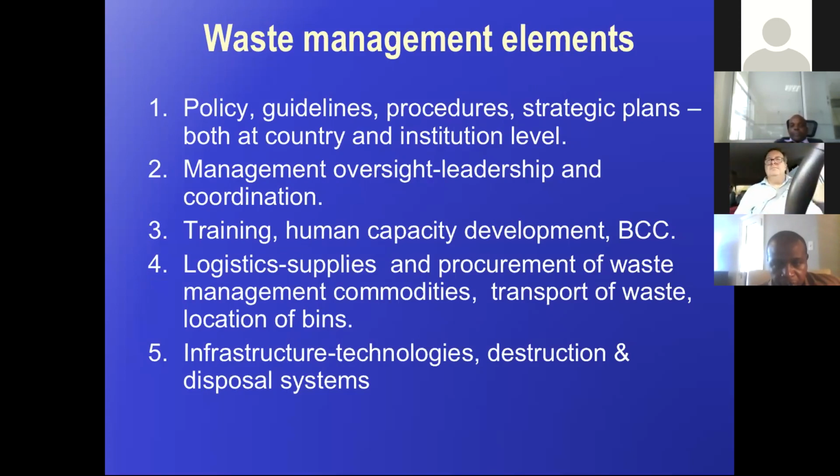And one of the shortfalls that I've seen in a lot of different places is that the treatment technology, which is usually the incinerator, will be addressed and procured, and initially the incinerator will work well, but then there will be gaps. The personnel might not be trained properly, the equipment might need to be maintained, or certain components will break down. And without these different elements in place, it results in a treatment process that's truly not sustainable. That's going to be short-lived and result in a broken system.